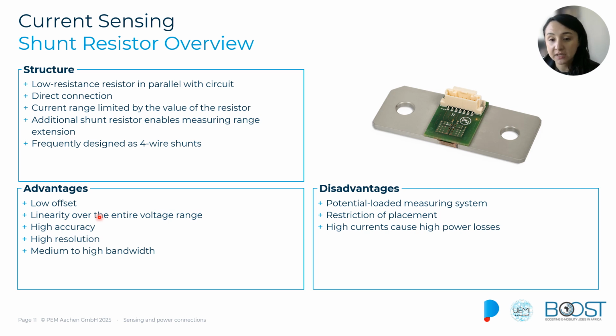That makes them very easy to process. When made with high quality materials, like manganese or nickel chromium alloys, the shunt maintains a precise characteristic and impedance across a wide range, and is independent of temperature. That's the reason why it has such good accuracy and resolution.